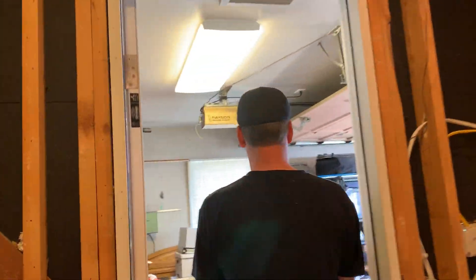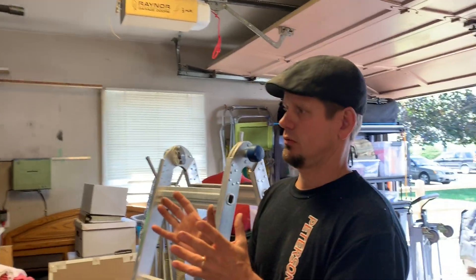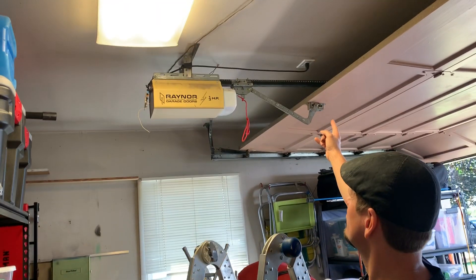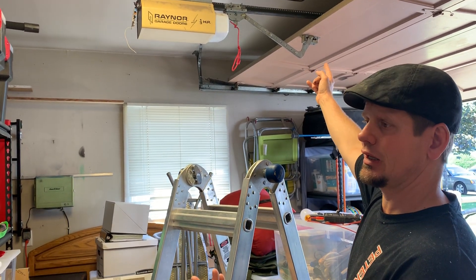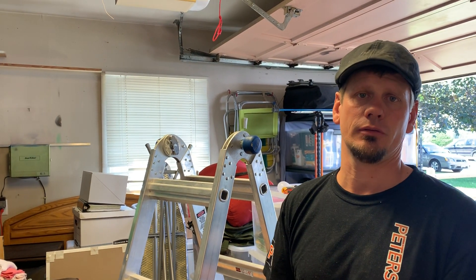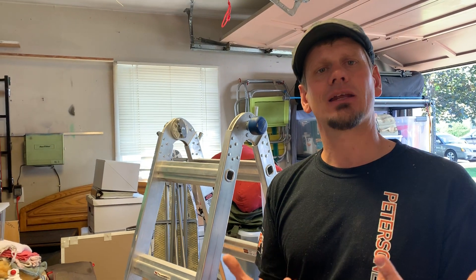The code doesn't state that every part of the circuit has to be protected. That's why you can have a master and a slave — what we call line and load, or upstream and downstream. You can have a device in the panel that just has a reset button on the breaker and you're good to go. In 2019 I did this whole garage — I didn't want to put GFCIs everywhere, so I ended up with four of them in this place.